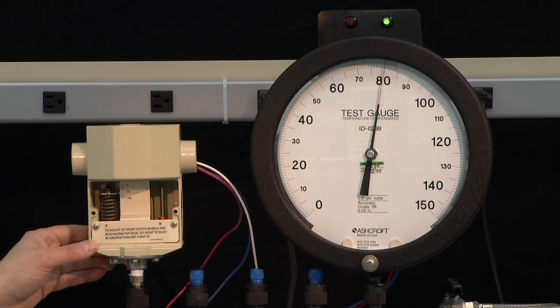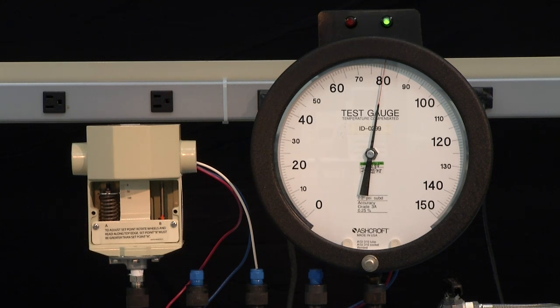Now we are set at approximately 80. To verify this, we are going to lower the pressure to zero, and then bring it up and see where the switch exactly turns on.